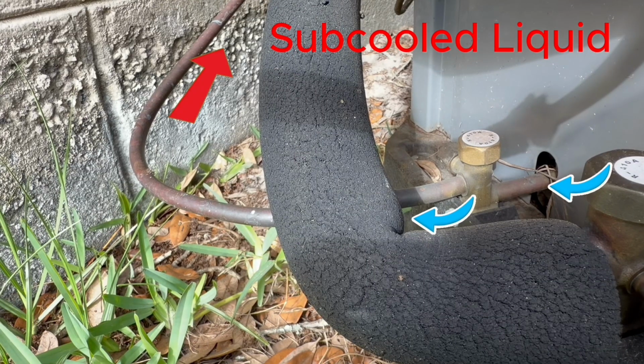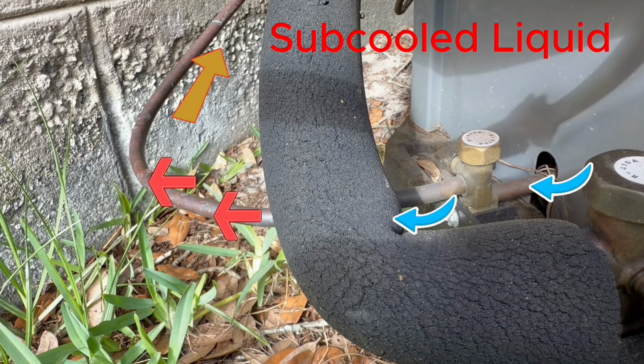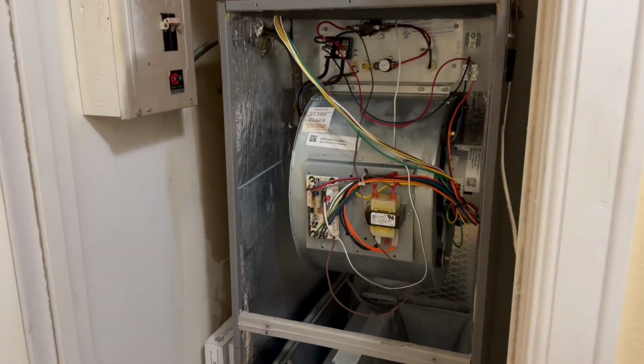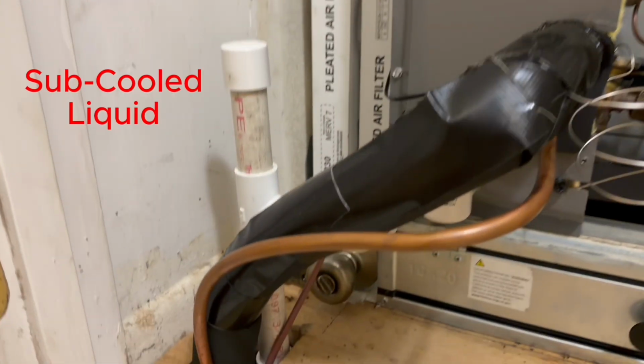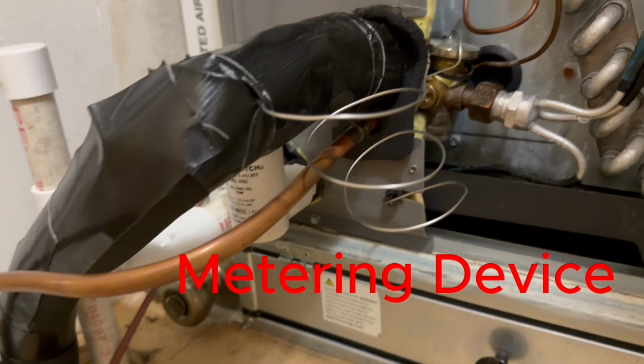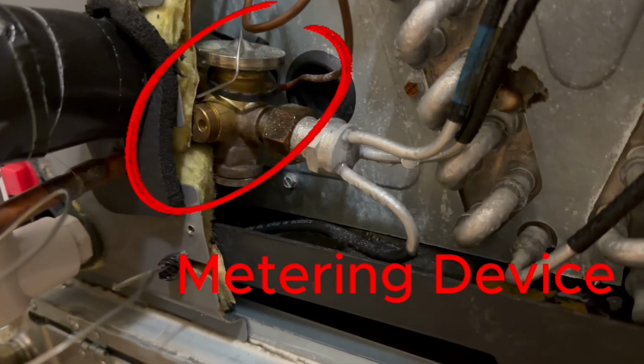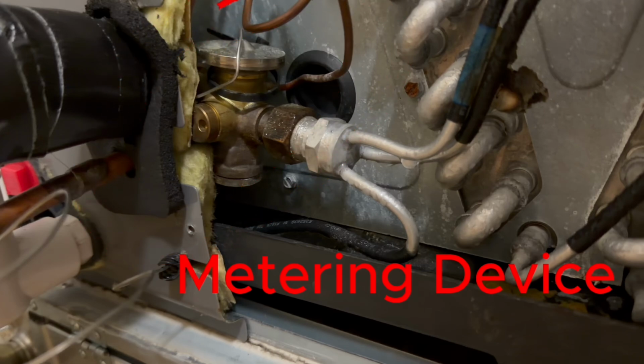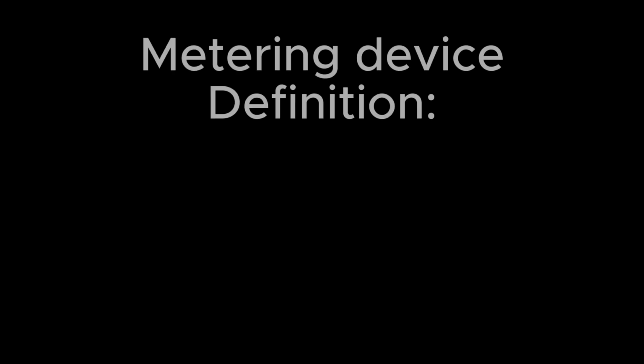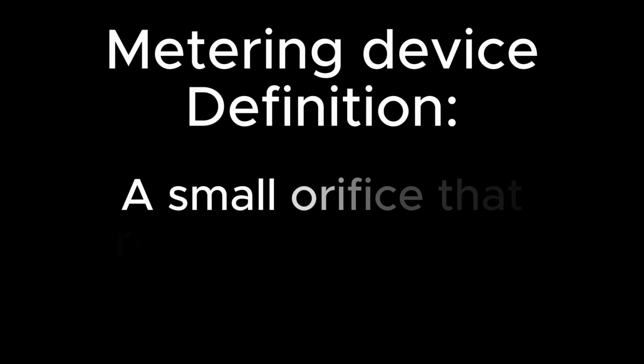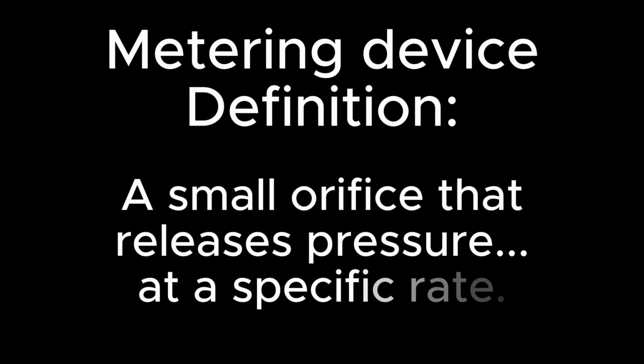Once the subcooled liquid has been discharged from the outdoor unit, it will then be piped into the indoor or evaporator coil. The subcooled liquid refrigerant will then encounter a metering device. The metering device is simply a small orifice that releases pressure at a specific rate.